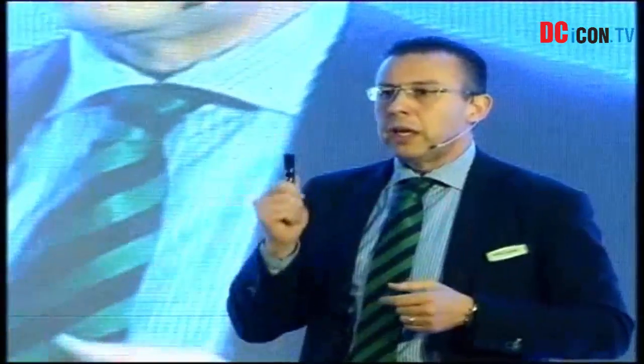And the global power of the PFC according to the line or installation you have, we provide in the catalog, though it's not shown here. We have a table showing your starting power factor situation and your target. You cross them, find the multiplier, and that multiplier times the total power of your installation gives you the number of kilovar to put in parallel with the line.